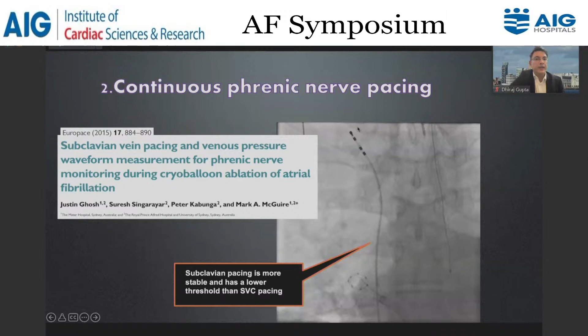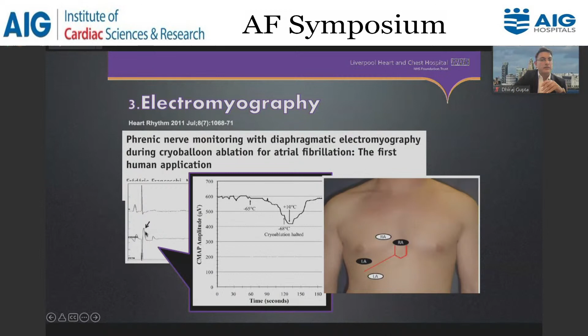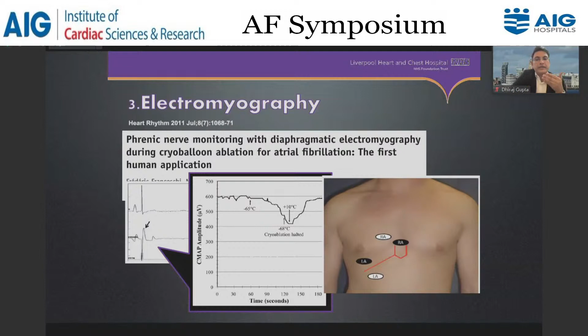Electromyography, again, this is something which has been increasingly used. It gives you a visual interpretation of the diaphragmatic pacing. So it's very simple. All you do is you lead one, you swap it around. So you put the left arm here below the diaphragm, the right arm just at the base of the sternum, and essentially you're measuring the electrical activity across the right diaphragm. And that way you can see very clear signals on your EP screen. And that means that when that signal starts going down, then you know that you are losing activity of the phrenic nerve, and that is the time to stop.